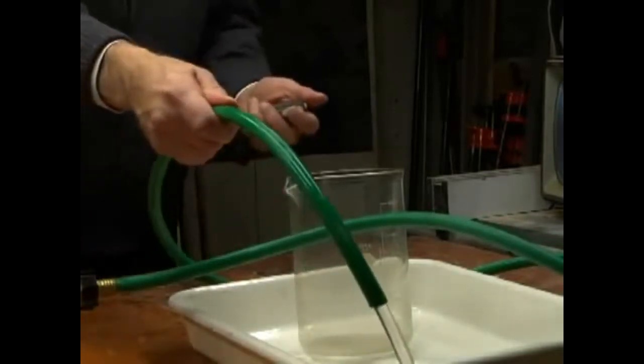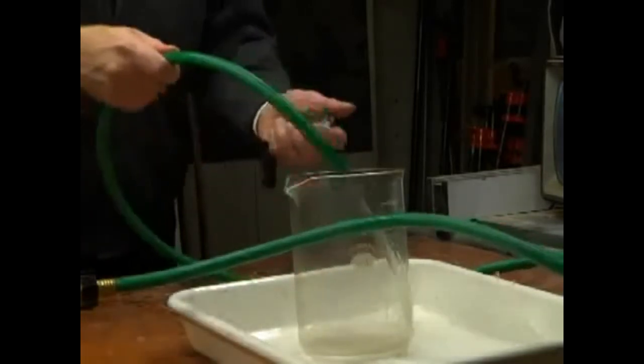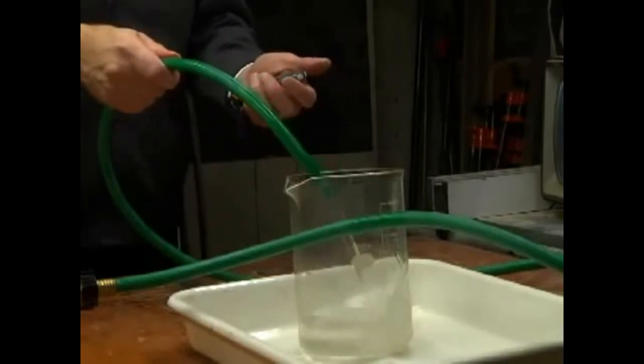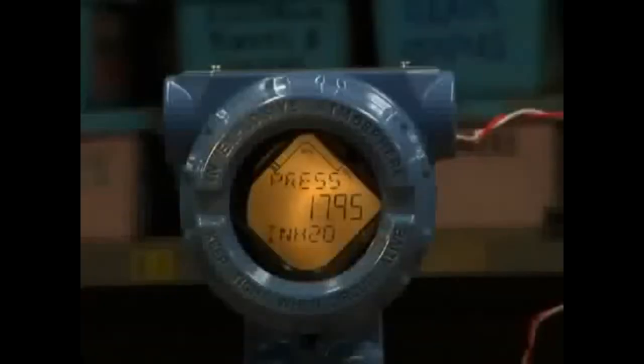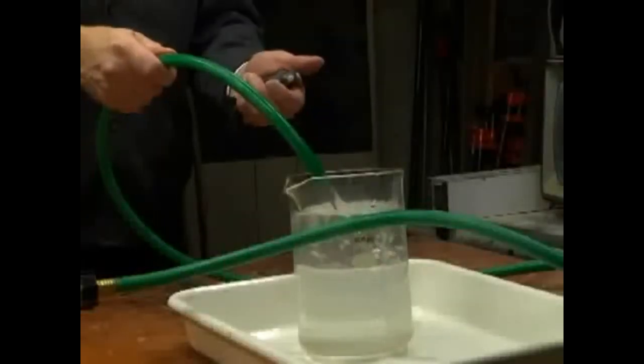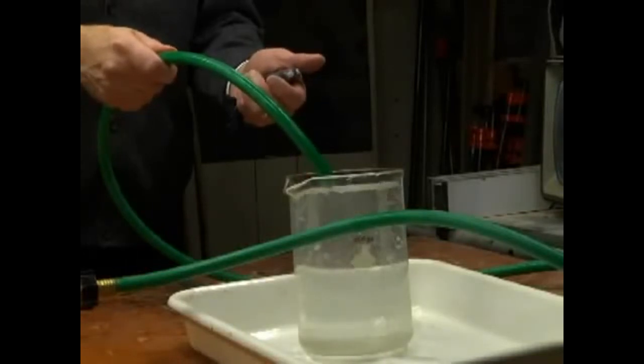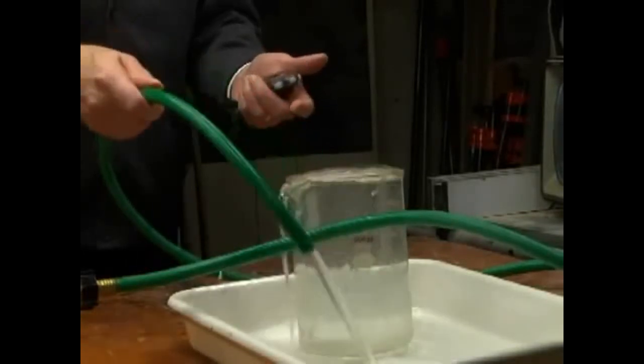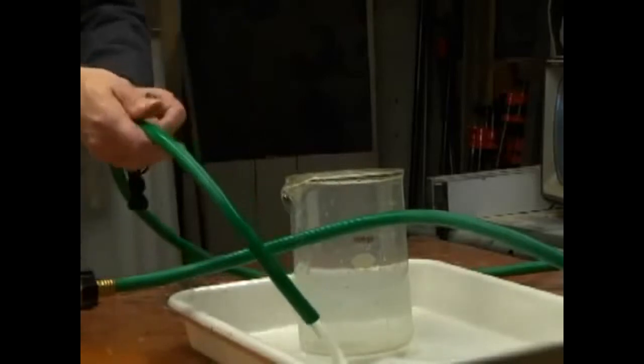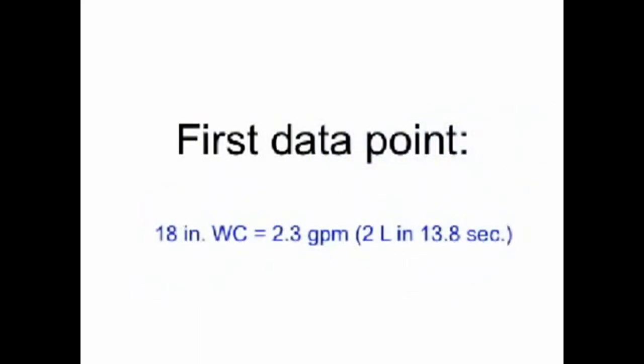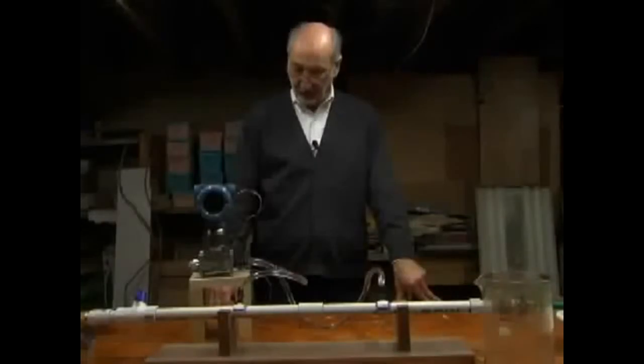Okay, ready, start. There. So it took 13 seconds to fill our beaker. So now we have one data point to start creating our flow versus differential pressure curve.